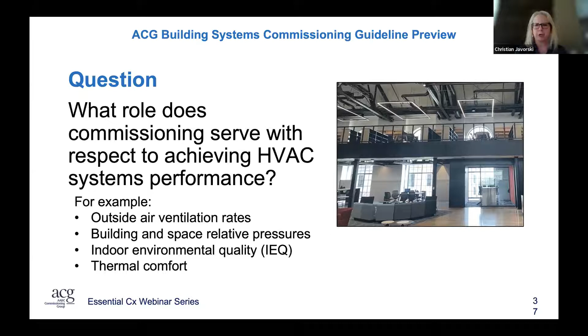So what role does commissioning serve with respect to achieving HVAC systems performance? This is very important and critical. The HVAC system and control system is what allows us to control things to provide the designer's intent and the owner's requirements. When we get into the technicalities of outside air ventilation, relative pressures of the building, IEQ, and thermal comfort, these are all really important. I term it like a super QC through documentation and processes to try and achieve all these things, because that's when we really figure out whether or not we did our job—at the end of the project.